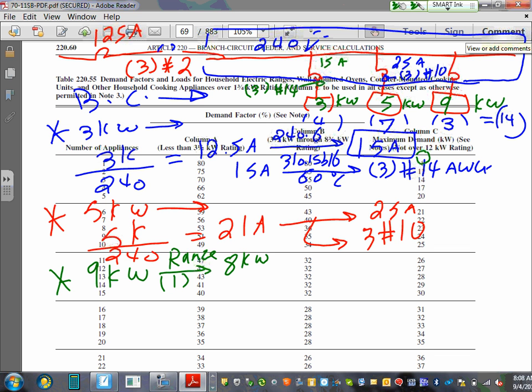Okay, so I used the 9 kW for one range, give me 8 kW. Then I size everything for 8 kW now. So let's go size everything for 8 kW. 8 kW divided by 240. Everybody knows why the 9 became an 8? Why did the 9 become an 8? What note is that? This is note number 4: it shall be permissible to calculate the branch circuit load for a range according to Table 220.55. Done. Okay, so can somebody give me an answer for this, please?